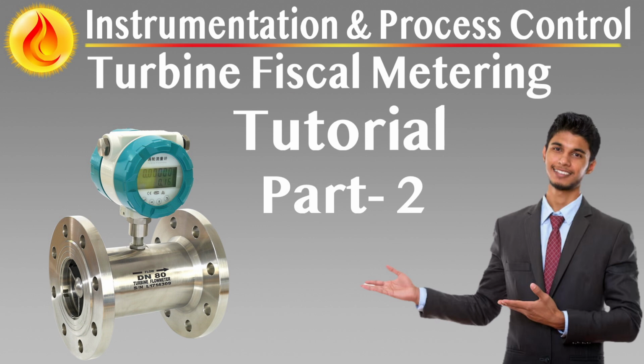All piping and valve materials must be selected based on compatibility with the specified process conditions: pressure, temperature, chemical composition, and cleanliness. Wetted components such as turbine meters, strainers, and instrumentation must be constructed from materials that prevent corrosion, erosion, and stress cracking under long-term exposure. In hydrogen sulfide or other corrosive services, specialized alloys such as stainless steel, Monel, or Hastelloy may be required.